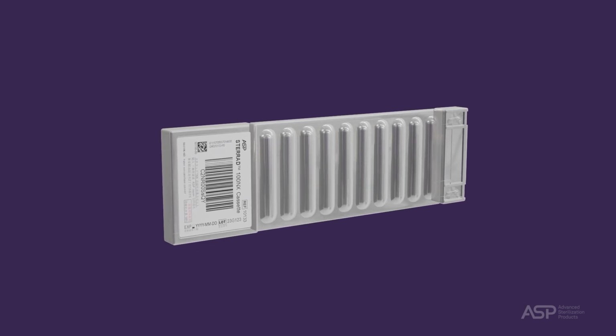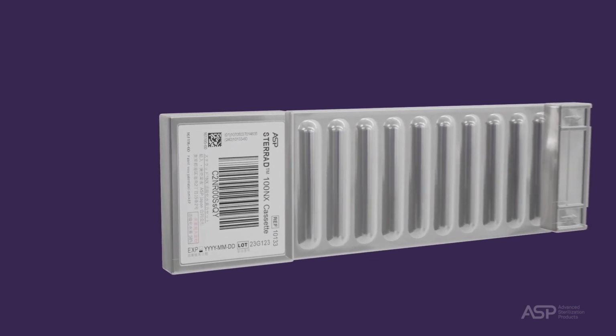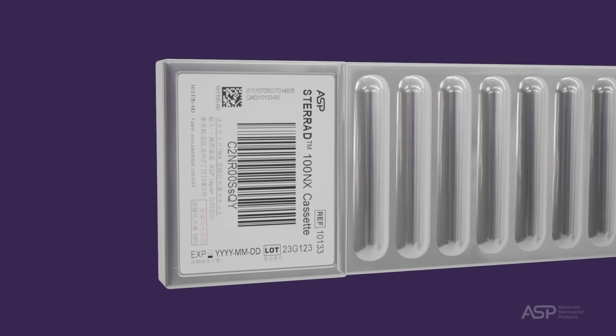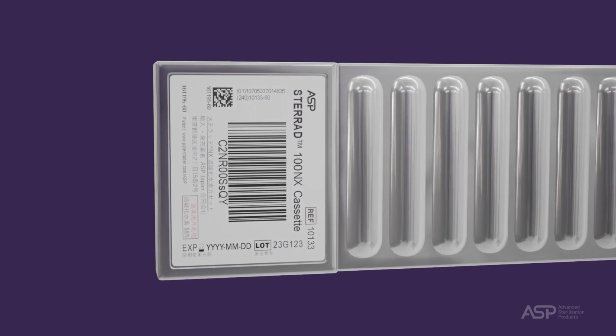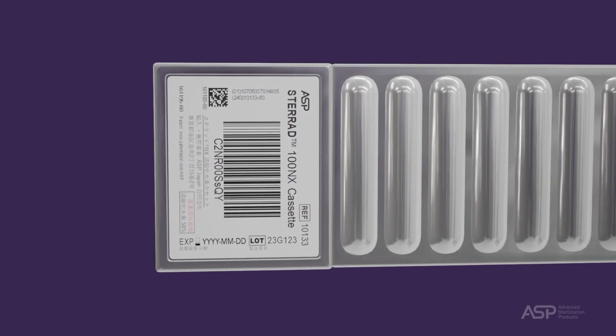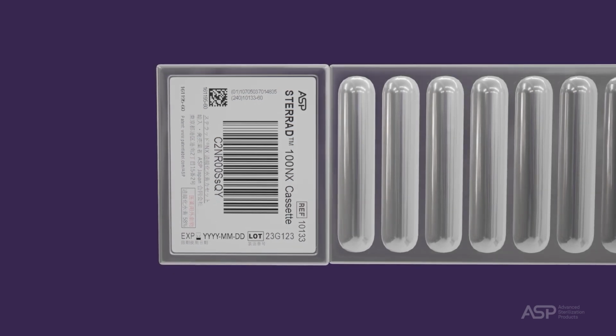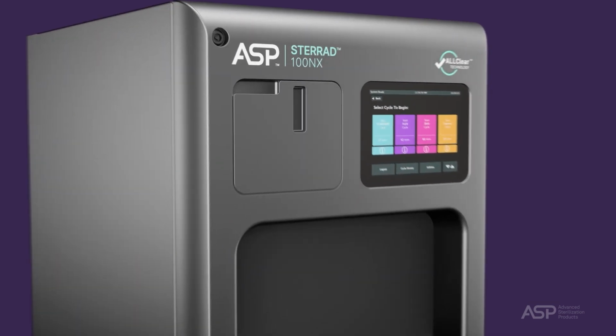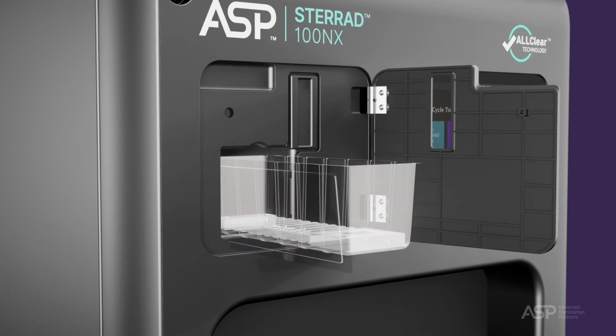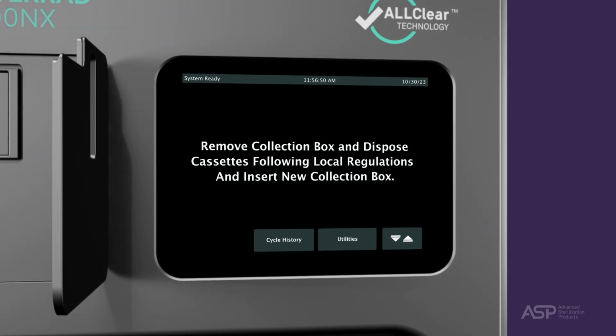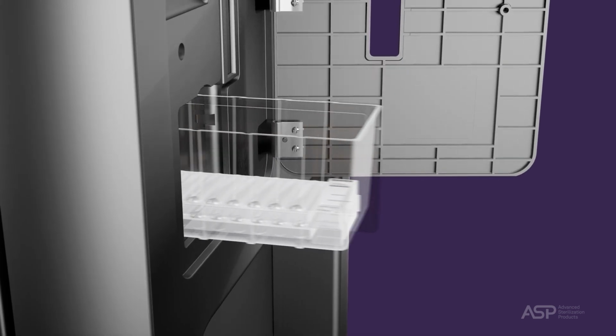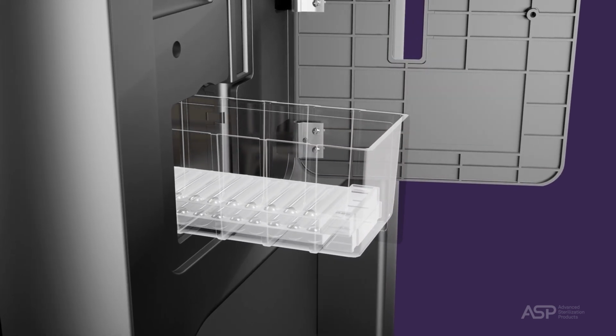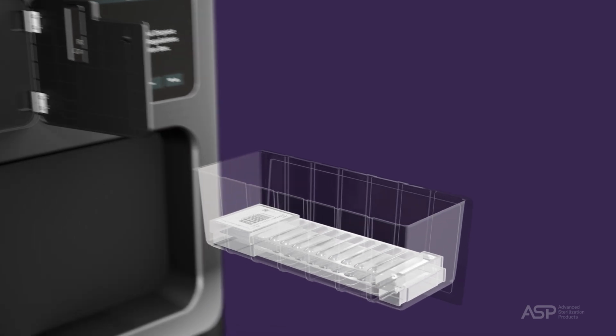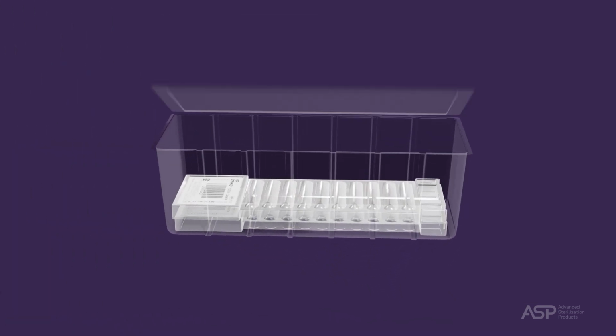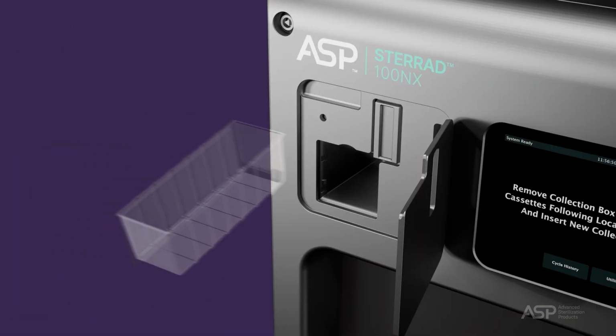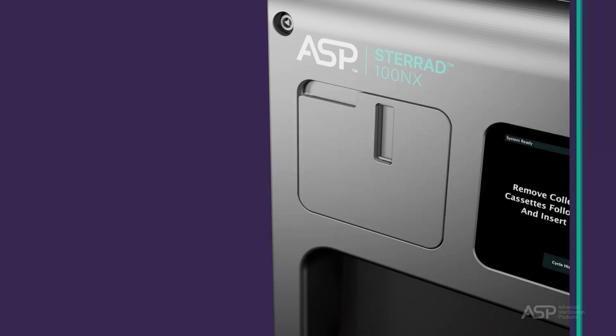The use of the cassette in the STERRAD 100NX Sterilizer with ALLClear technology is controlled by the RFID label. The label limits the use of a cassette to the appropriate sterilizer and ensures that cassettes are not used beyond their shelf life. When a cassette is empty, the sterilizer automatically moves it to the cassette disposal box. The screen displays a message instructing you which actions to take next. When the cassette disposal box contains 2 cassettes, it is full and you must dispose of the full cassette disposal box. Never reuse a cassette disposal box. Once removed, a new cassette disposal box must be inserted.